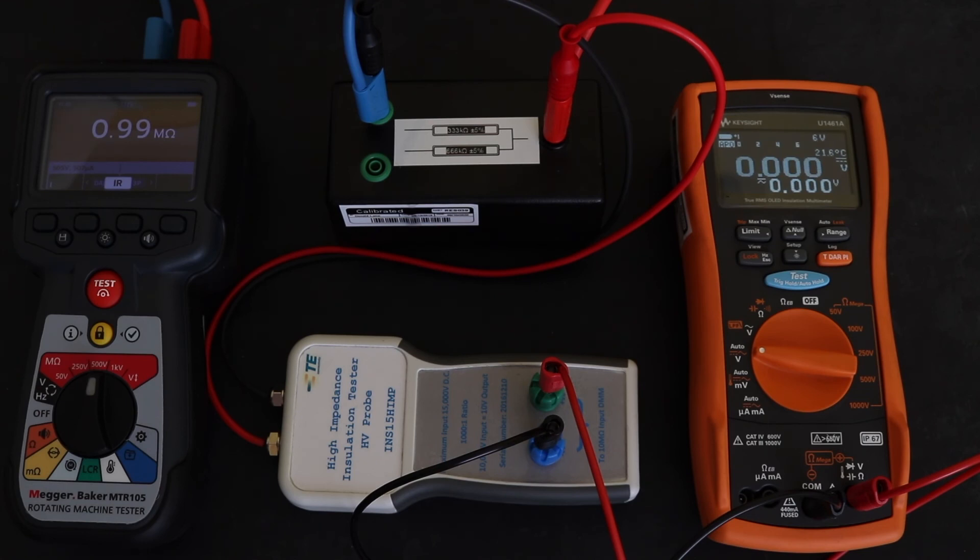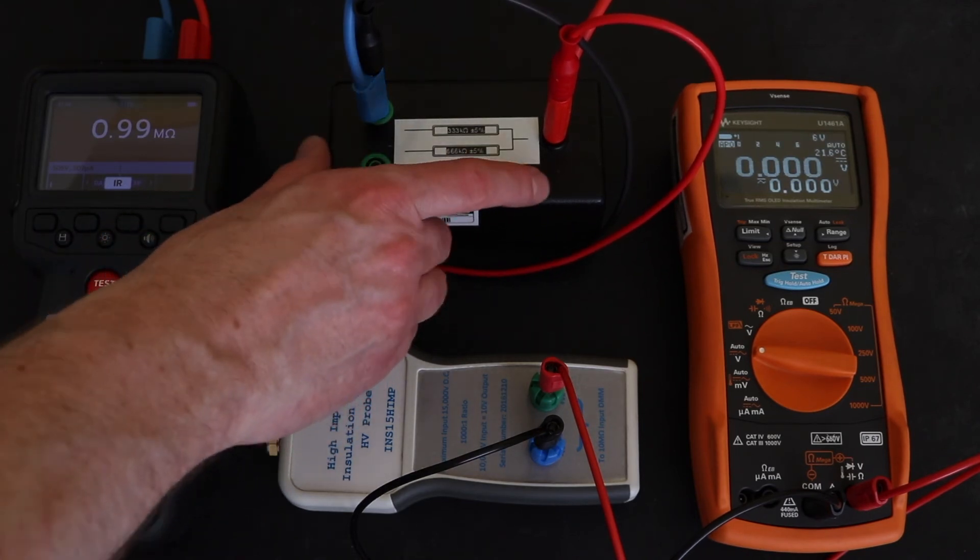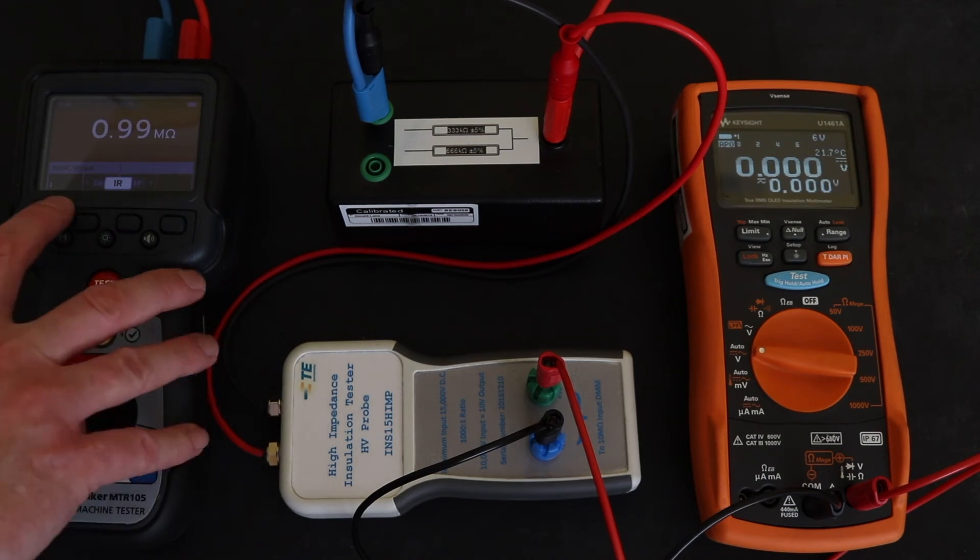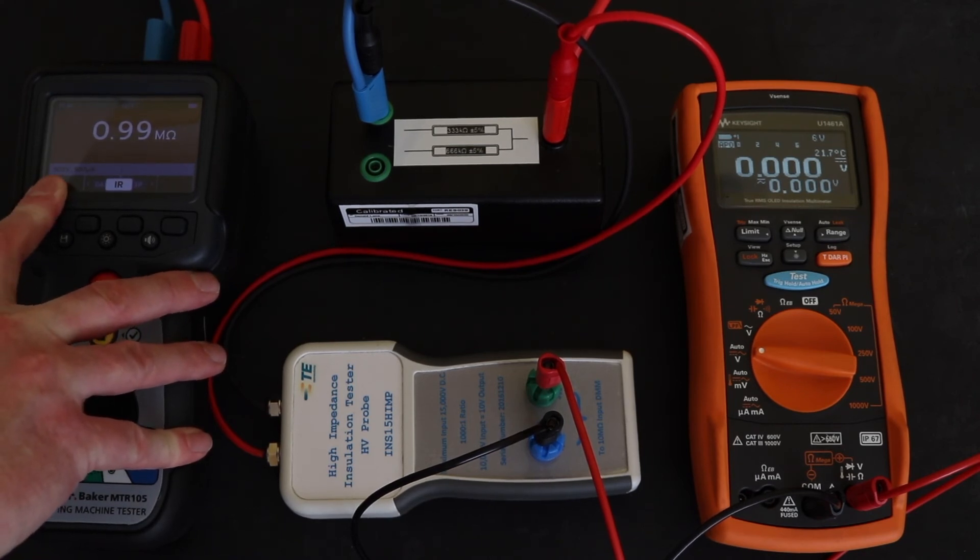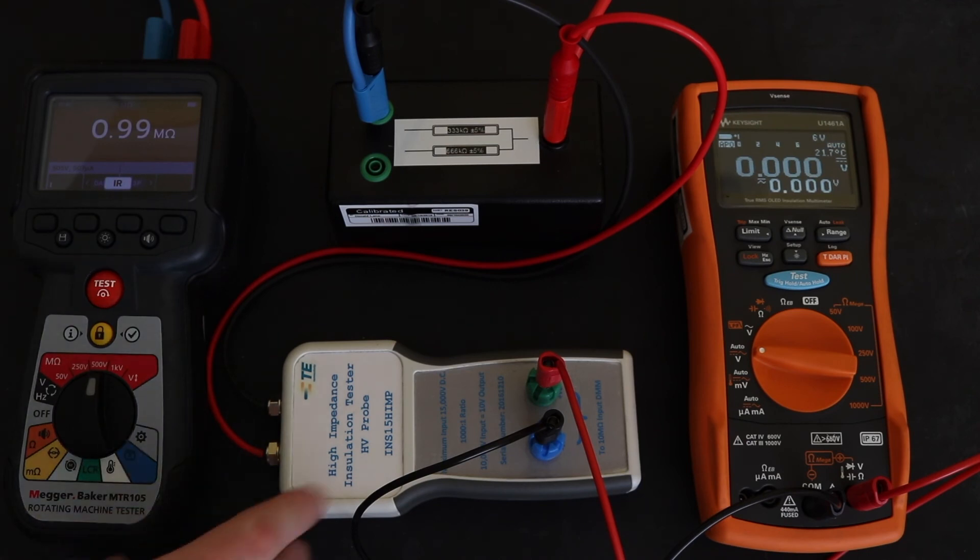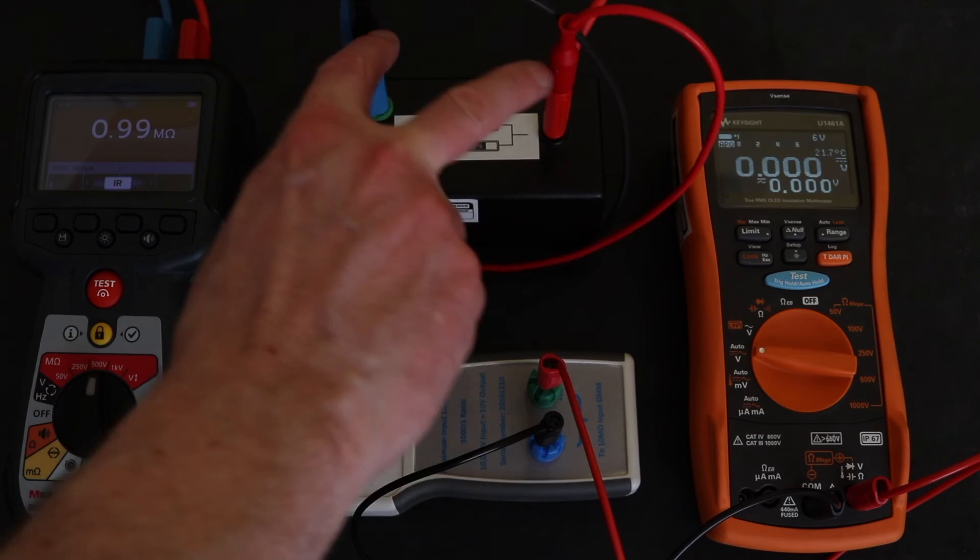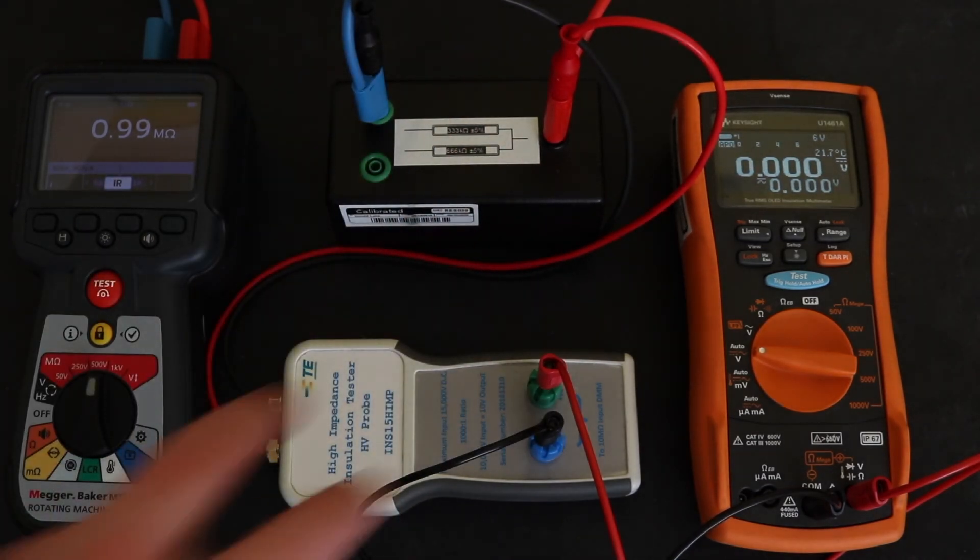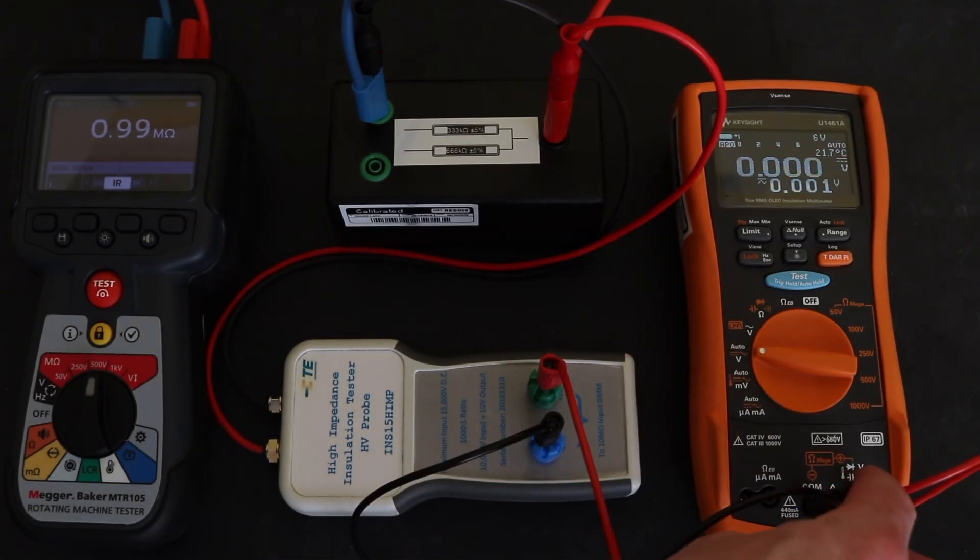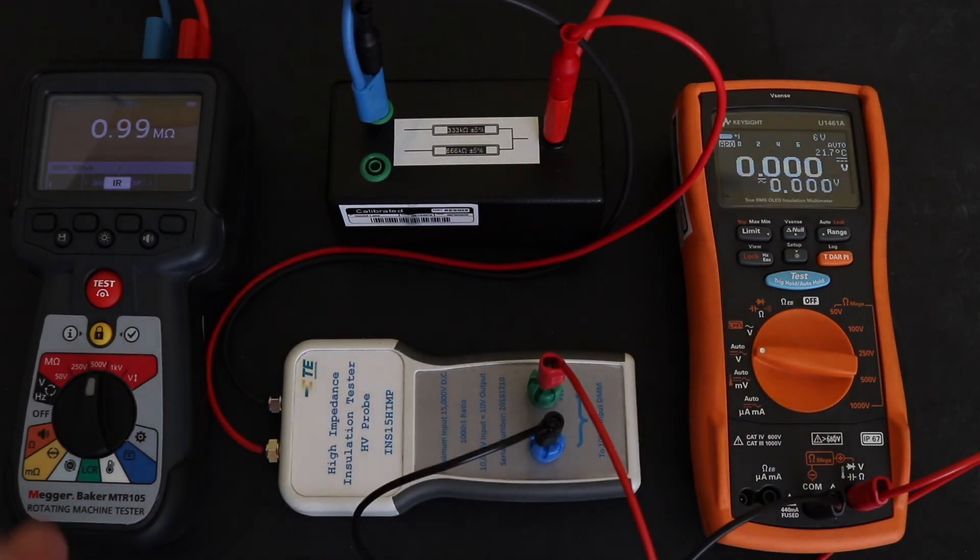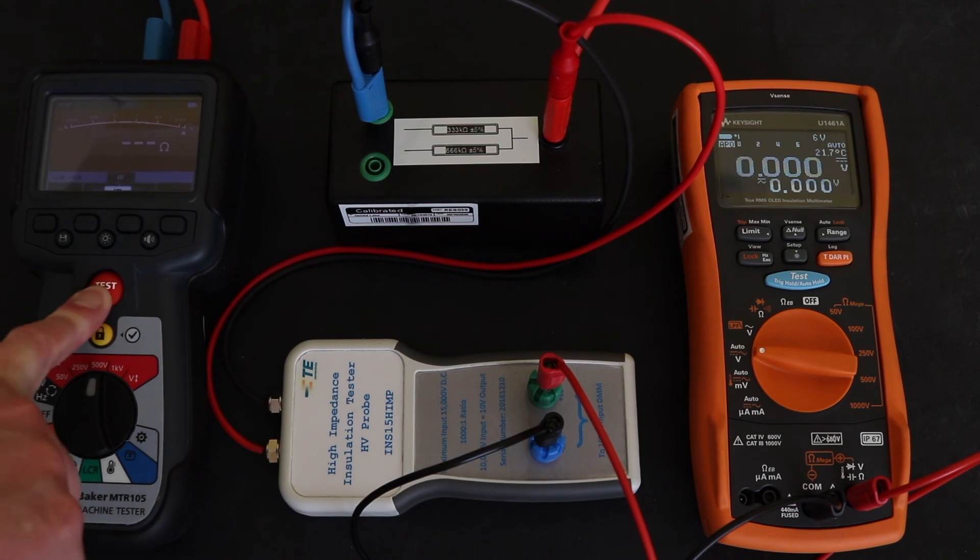So this is a test setup for measuring the voltage regulation from the output of the insulation tester. Personally I just do this at 500 volts, you can pick any test voltage on the instrument you like. I have a set of fixed resistors, some of them are in boxes of their own and some of them I use from the actual 5069 calibrator. Two ways I can actually record the voltage: I can record it off the instrument itself. A lot of instruments these days do have that facility. If it doesn't have that facility, what I have is a high voltage probe which is just a big voltage divider. This is a 1000 to 1 voltage divider. I wire that straight across the output of the insulation tester which is across my test resistor, then I take this to an instrument that is set to measure DC volts which will measure the reduced output from the voltage divider and then I times the value seen on this via the ratio. So I'm on 500 volts there, this is actually using the 30k resistor, press the go button.